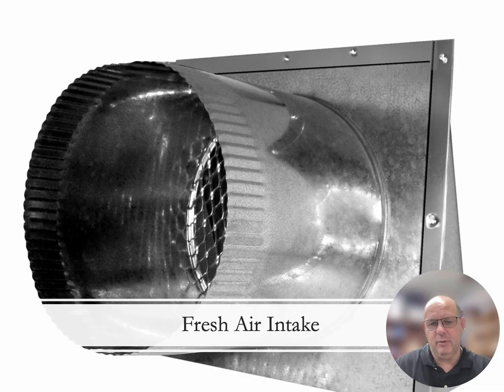Now, sometimes when you're dealing with different municipalities, different locations, different codes, it may be required for us to bring in fresh air for that living environment or that office space. What we're going to do is duct it to the outside, and we're going to bring a fresh air trunk into the actual return piping of the system. As the furnace or the air handler turns on, it's going to take that air, suck it in from the outside, into the building.